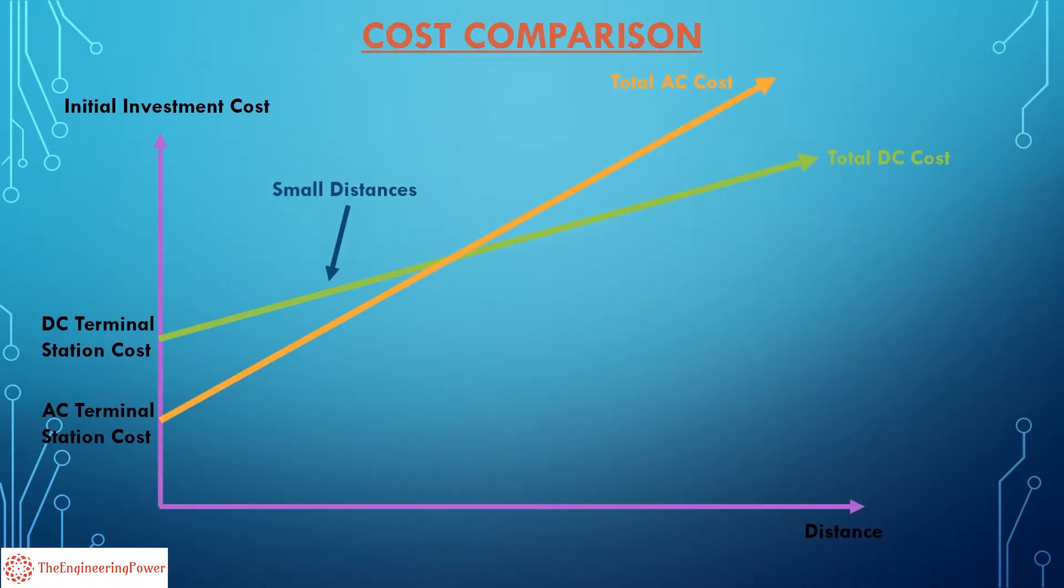For small distances, the overall cost of HVDC transmission system is greater than that of HVAC system. For a specific distance, HVDC system becomes cheaper than HVAC. This distance is called the breakeven distance. The breakeven distance for overhead transmission line is around 600 kilometers. That's one of the main reasons behind the use of HVDC transmission system for power transmission over very long distances. So one of the main criteria behind the selection of AC or DC system for power transmission is the distance over which the power needs to be evacuated.